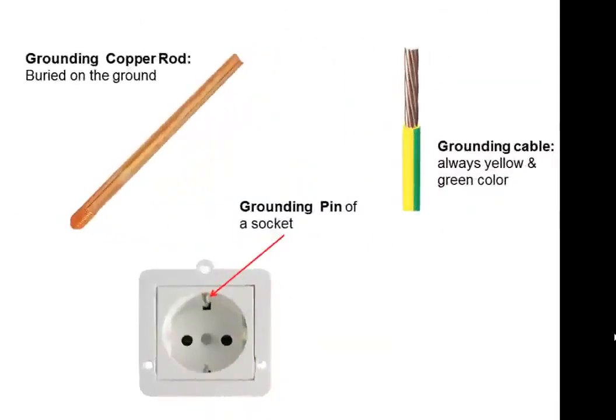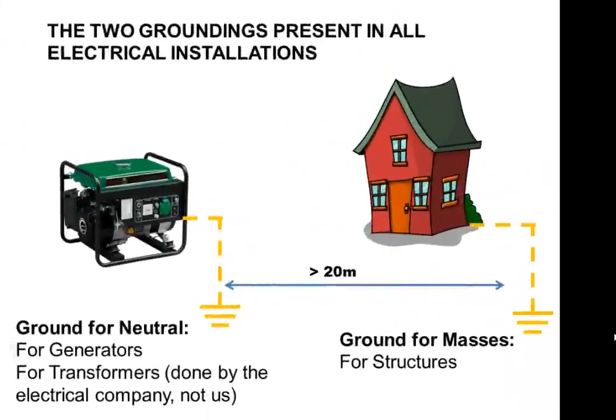A grounding system consists basically of a grounding copper rod, the green and yellow grounding cable in each circuit of the installation, and the grounding pin of the sockets and plugs. All structures must always have a grounding system for the masses. In case there is a generator, it should also have its own grounding for the neutral. These two groundings should always be independent and not connected between them, and installed at least 20 meters away from each other. Transformers also have grounding for the neutral, which is installed by the electrical company, never us.